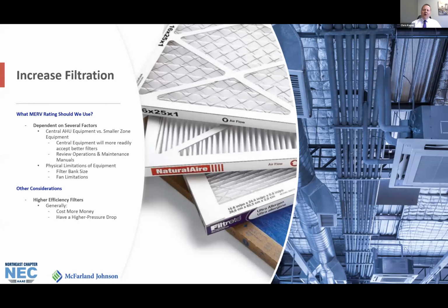Break out your equipment O&M manuals to see if the manufacturer offers a suggested maximum filter efficiency. The physical size of your equipment's filter racks will also provide some limitation to the type of filter you can upgrade to. ASHRAE recommends a MERV 13 or higher filter whenever possible. Cost, general rule of thumb is assuming your HVAC is served by standard efficiency filters today, your cost for filters is probably going to double when you make the move to the higher efficiency filters.